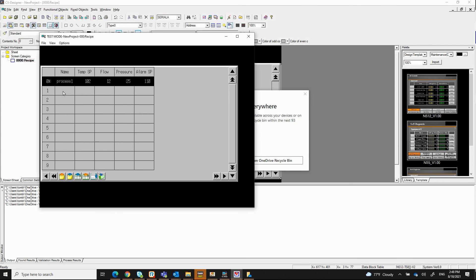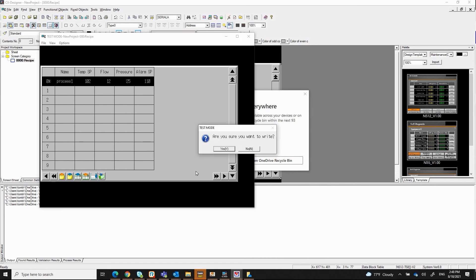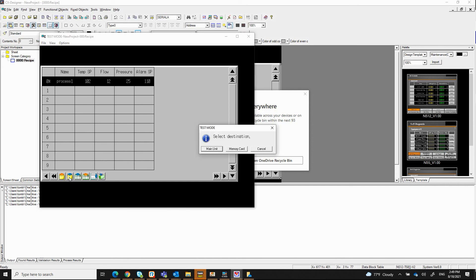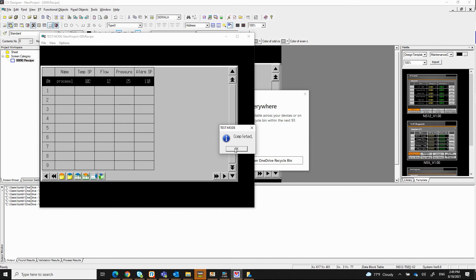If I want to write it to the PLC, I can. I will click this and it will transfer to the PLC. If I want to save to the memory, I will click this icon. And it will ask me, do I want to save it to the memory of the touch screen, which is this icon here, or if I have a memory card on the HMI, I will click the memory card and it will save that to the memory card. So I'm going to try the memory card. So it's completed, it's done.